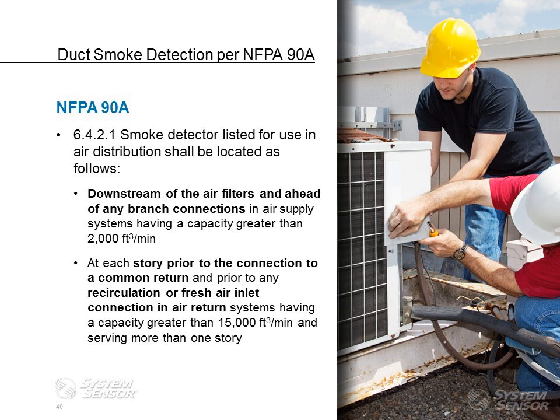And again, smoke detectors listed for use in air distribution shall be located as follows: downstream of the air filters and ahead of any branch connection in air supply systems having a capacity of greater than 2,000 CFM, and at each story prior to the connection to a common return and prior to any recirculation or fresh air inlet connection in air return systems having a capacity greater than 15,000 CFM and serving more than one story. So you can see here, per NFPA, depending on the size of the unit, if it's greater than 15,000 CFM, the standard says it's going to be supply and return. If it's less than 15,000 CFM but greater than 2,000 CFM, then it's on the supply side.